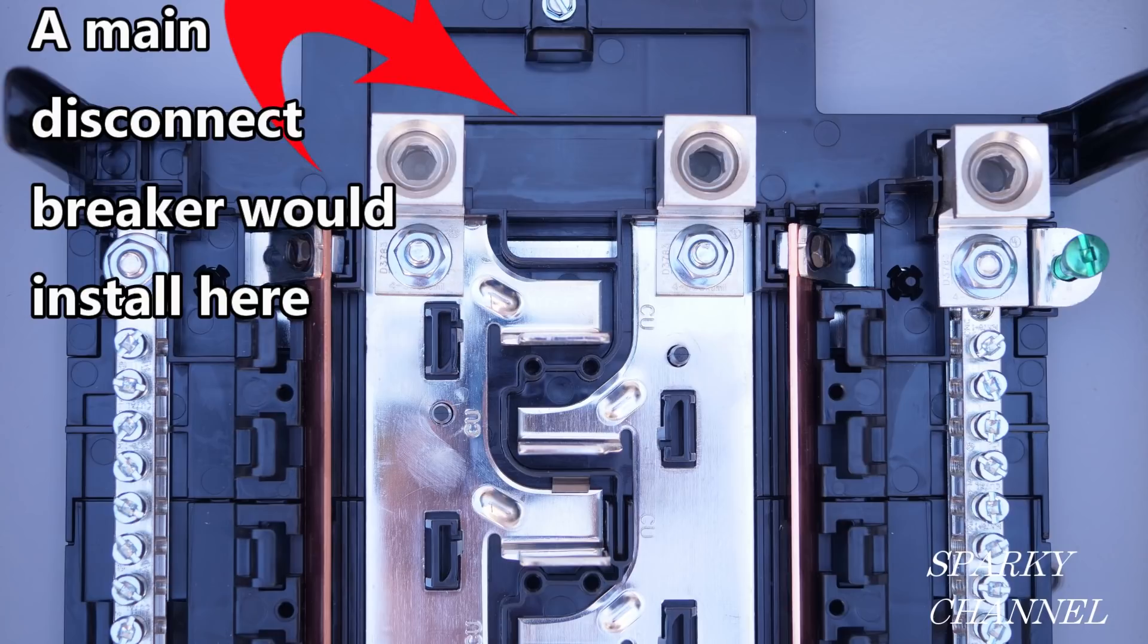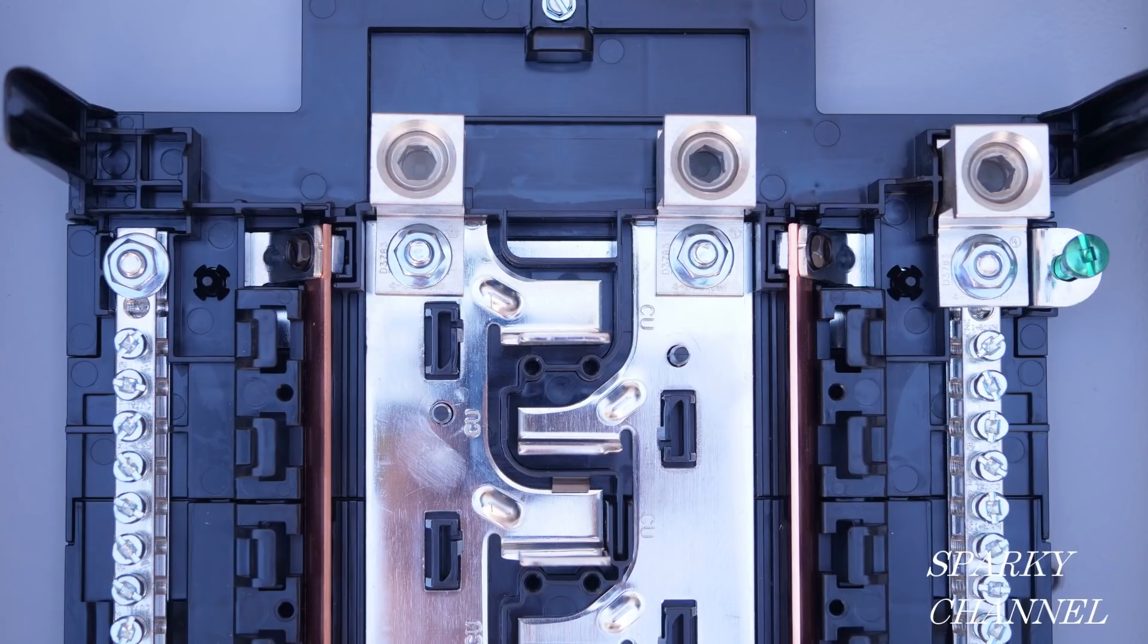If you'd like to add a main disconnect to this load center and use it as a main panel, and this panel is then your system's first disconnect, then you will need to screw in the green bonding screw.